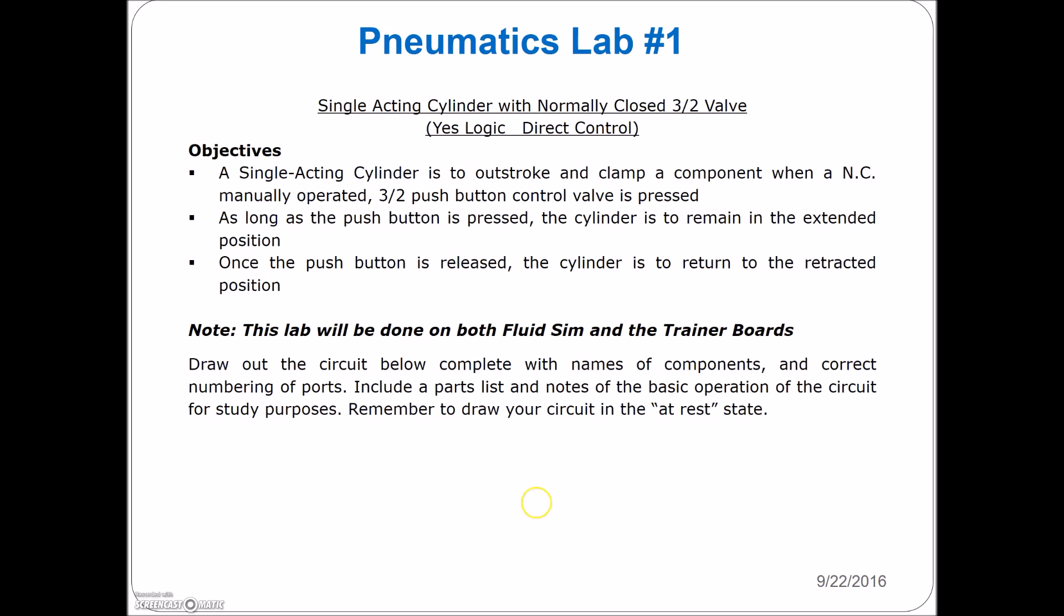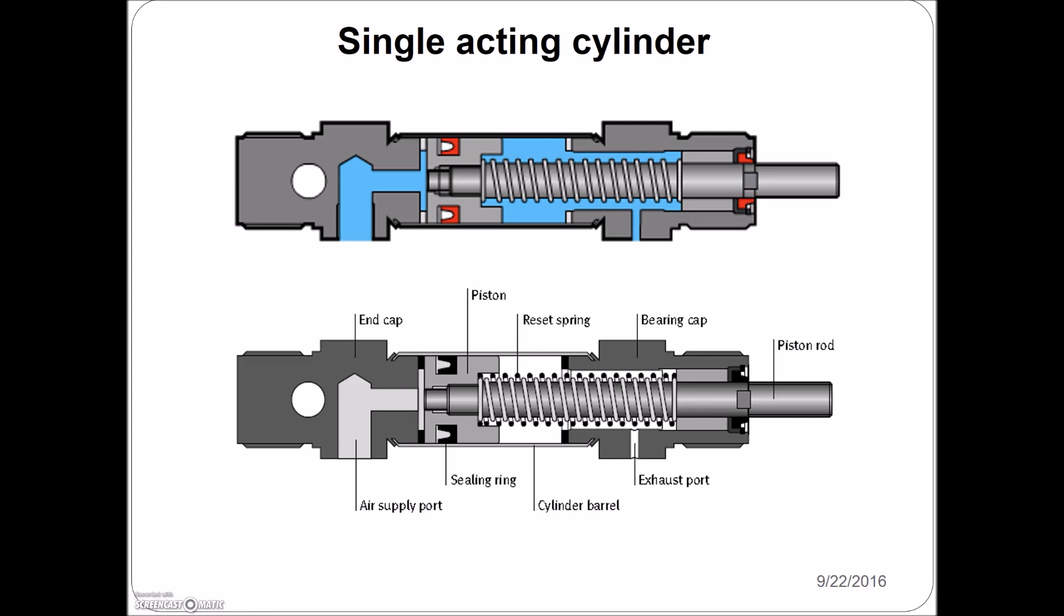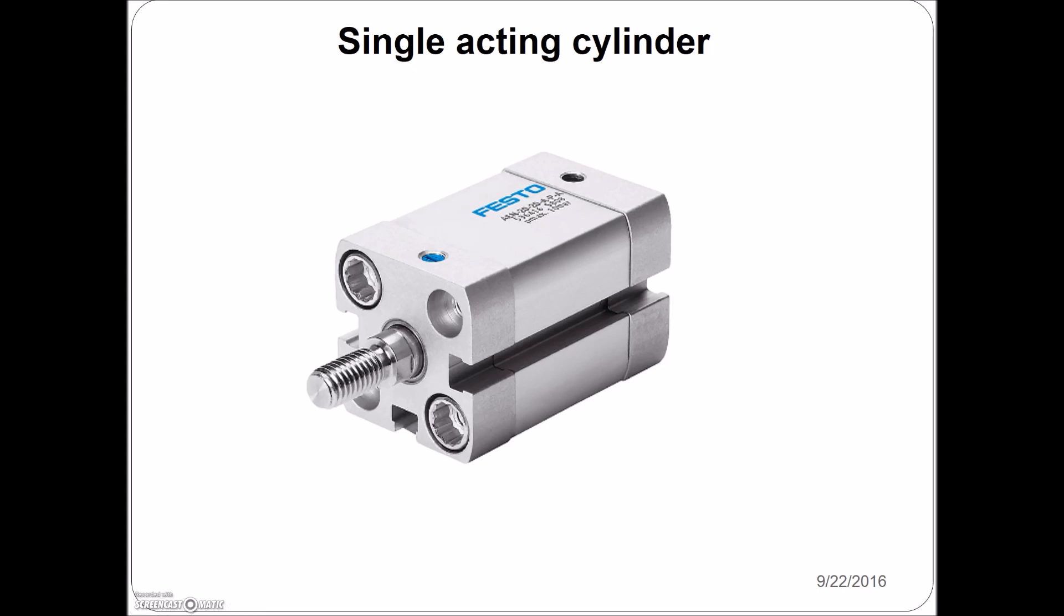Okay, so let's see. We need a normally closed push button, and we need a single-acting cylinder. Single-acting cylinder looks like this, where it has the one port. When we put that air to that one port, it's going to push against the spring and extend the cylinder. Once we release that air from the cylinder, then the spring retracts it to the initial position. Okay, so this would be your rest position for the single-acting cylinder. Looks like this, single port. Once you put air to here, then it's going to extend this cylinder.